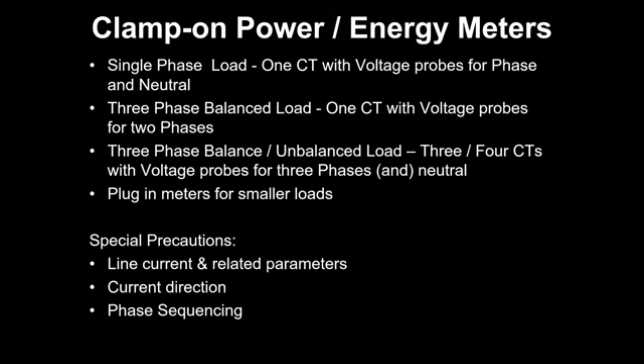Most of the meters will have similar accuracy, of course. The workmanship and other things could be different. Now this CT is available in 2 or 3 different ranges for the three-phase balance meter. It could be 600 ampere, 300, or 100 ampere. So we need to be slightly careful when selecting the meter. What is the maximum current, or the maximum load, we are going to measure with this? Accordingly we need to select the meter. Otherwise, as I said earlier, if you have a 600 ampere CT and you're measuring 20 ampere, 5 ampere or 6 ampere, it will not come out correctly, and there could be an error. So we should select the CTs accordingly.